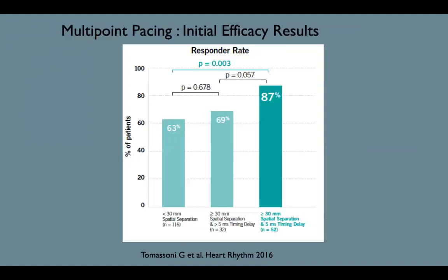So if we think about how it actually works, this is the initial efficacy study from St. Jude, now Abbott, looking at multi-point pacing. You can see that what they've done is looked at the optimal spatial separation of the leads on the left side. You still have a significantly good response to CRT with about 63%.